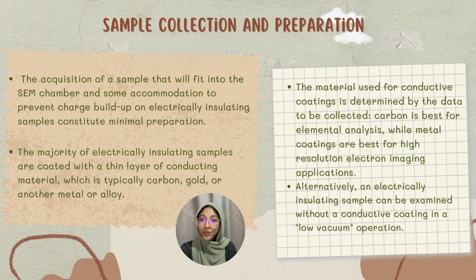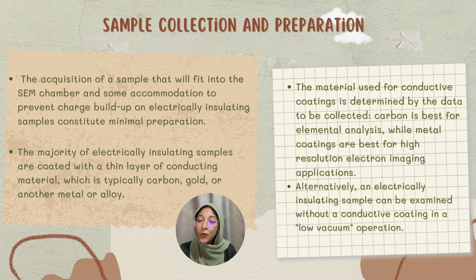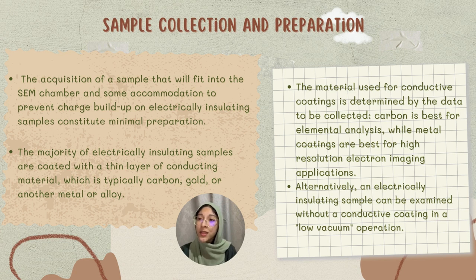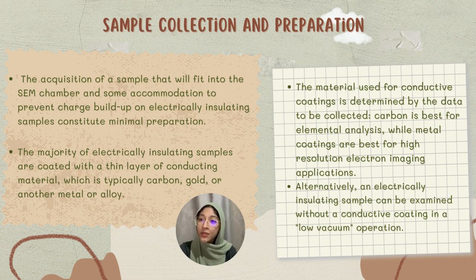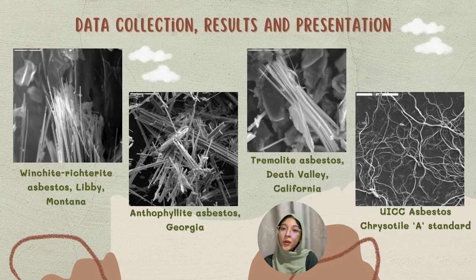For sample collection and preparation: the sample must fit into the SEM chamber, and some accommodation to prevent charge build-up on electrically insulating samples is required as minimal preparation. Most electrically insulating samples are coated with a thin layer of conducting material — typically carbon, gold, or another metal or alloy. The material used is determined by the data to be collected; carbon is best for elemental analysis, while metal coatings are best for high-resolution electron imaging. Alternatively, an insulating sample can be examined without a conductive coating in low-vacuum operation.